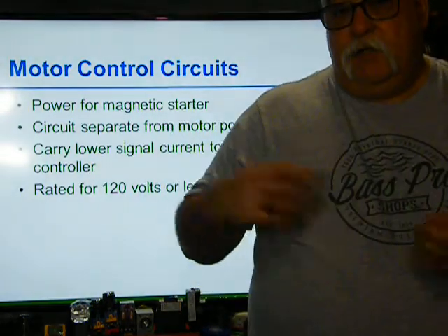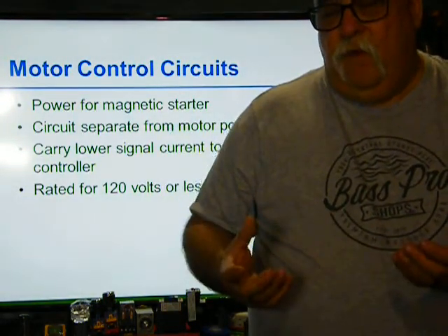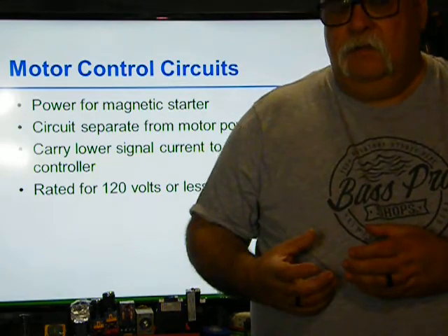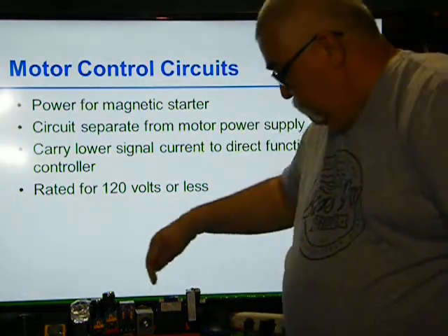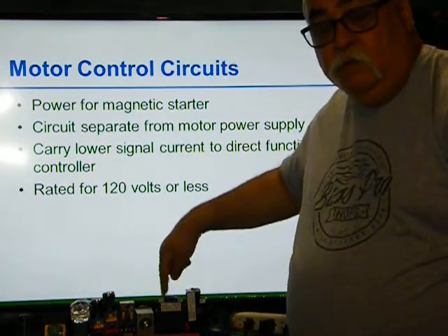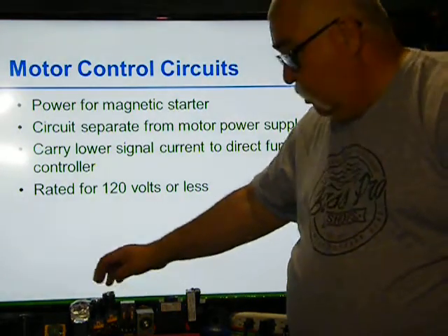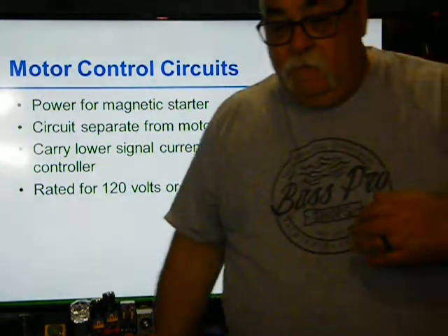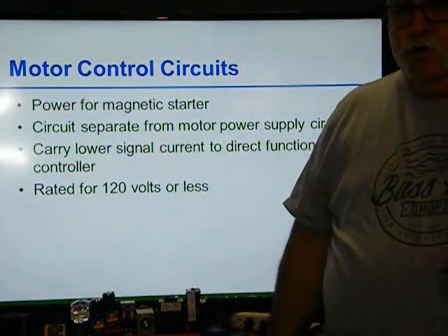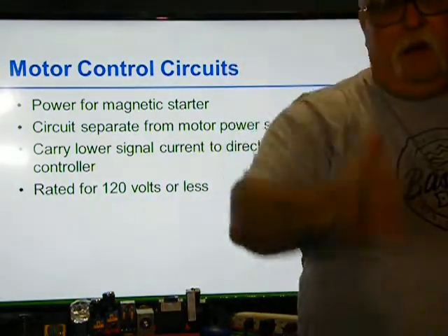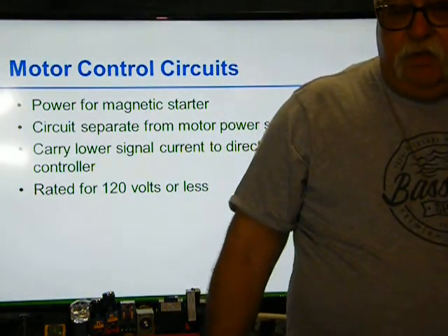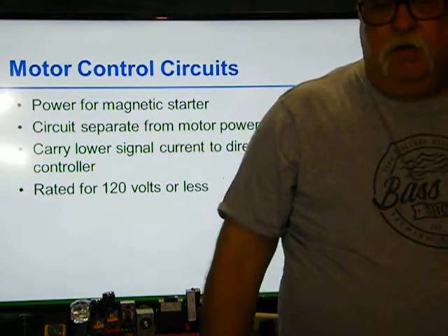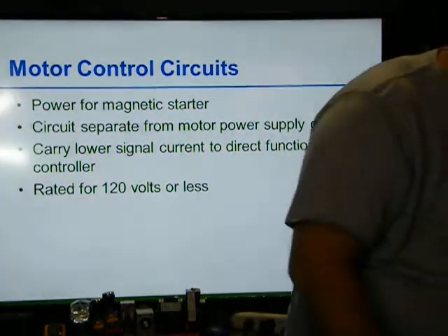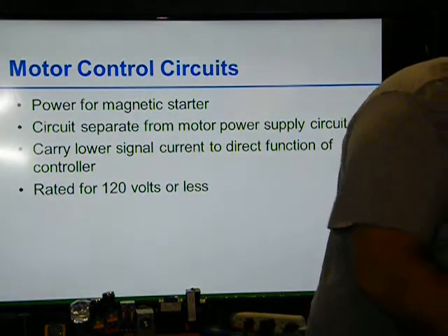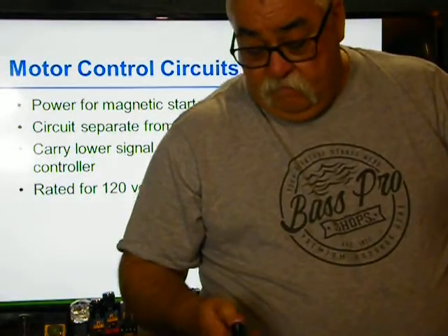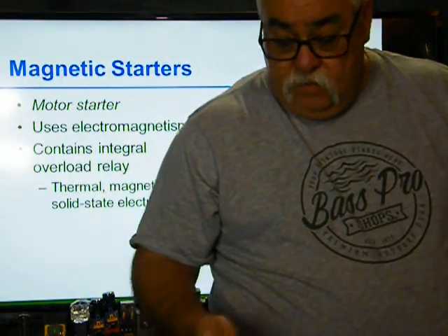It has overcurrent protection on both sides. Those transformers were only 50-watt transformers. That's it. It doesn't have to carry a lot, just the coil to open and close. And if these have lights, whatever the wattage of the lights is, that's the only current that would be running through the control circuit. So you can put a lot of controllers on one circuit. Why? Because there's a very small current.